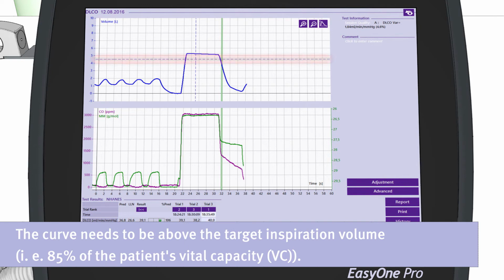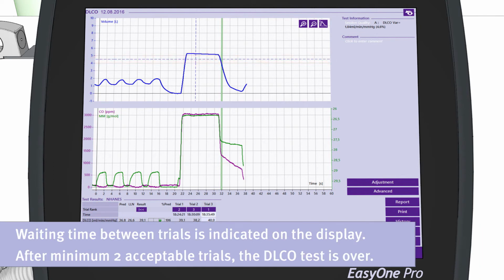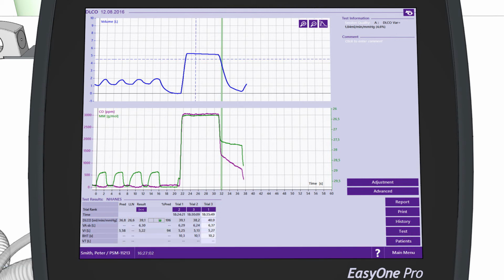The curve needs to be above the target inspiratory volume, which is 85% of the patient's vital capacity. The waiting time between trials is indicated on the display. After a minimum of 2 acceptable trials, the DLCO test is over.